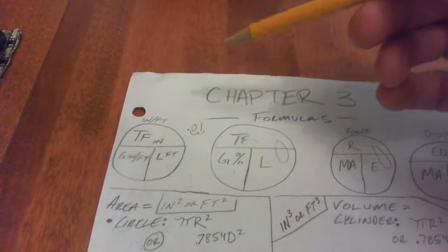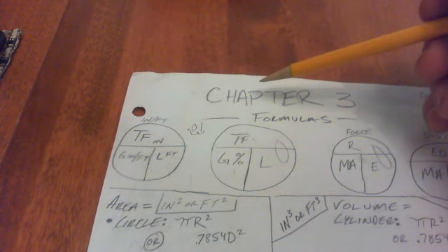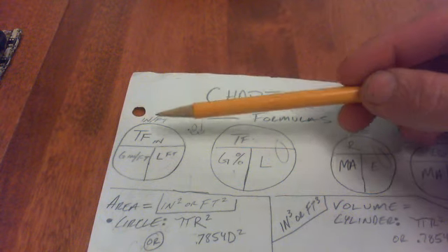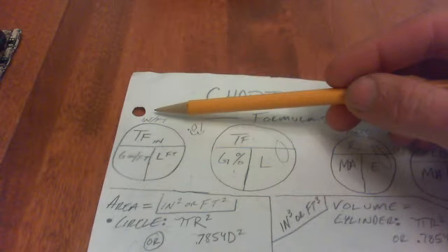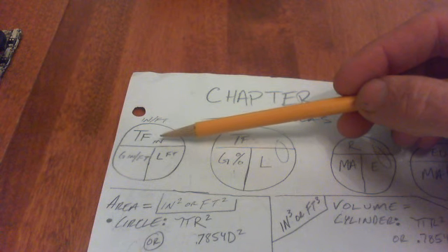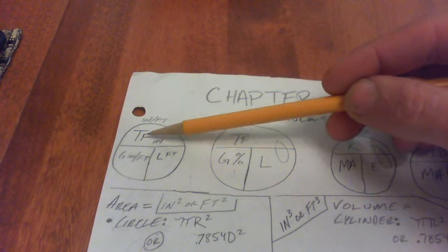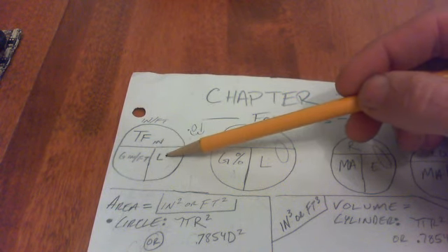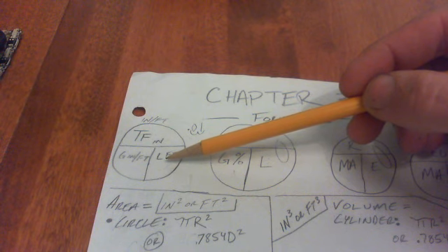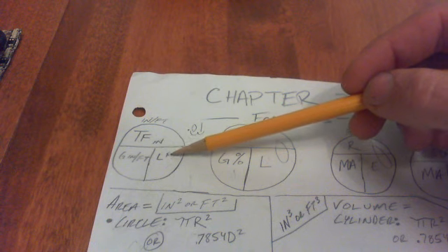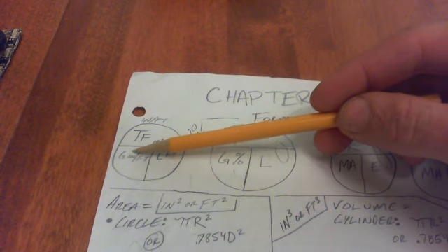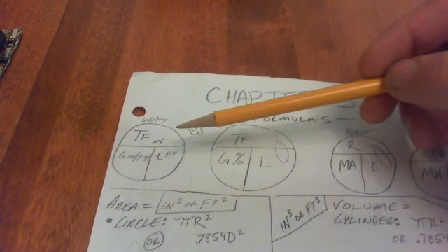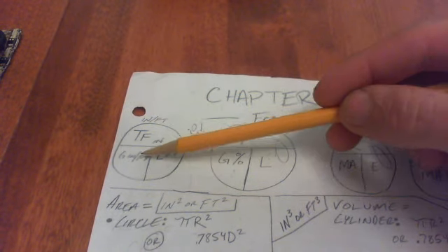In this video I'll go over the formulas that were given in chapter 3. So starting off with total fall, inches to feet. If you need to find that out in a particular problem, then you start off with total fall in inches up here, length, which can also be called distance or horizontal run. I plugged it in there, and those have to be in feet, and then the grade will be in inches per foot, or parts of an inch per foot.